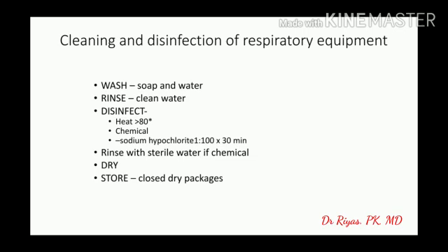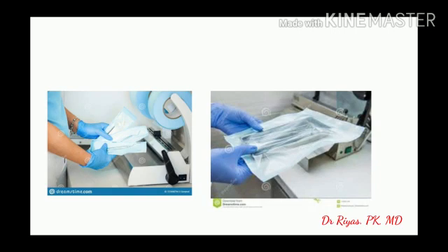Coming to cleaning and disinfection of reusable respiratory equipments, it should be initiated immediately after use. The process follows this sequence: wash, rinse, disinfect, rinse in sterile water if chemically sterilized, dry it and store it in sterile dry packages. Washing with water and soap removes secretions and particles in tubes. Rinse with clean water and disinfect with the appropriate method as directed by the manufacturer, either by heat sterilization, chemical or gas sterilization. In case of gas sterilization, you need to get those tubings dry before getting it done. Rinse with sterile water if chemically sterilized and dry it before storing in sterile dry packages.